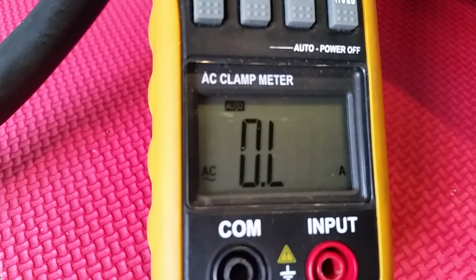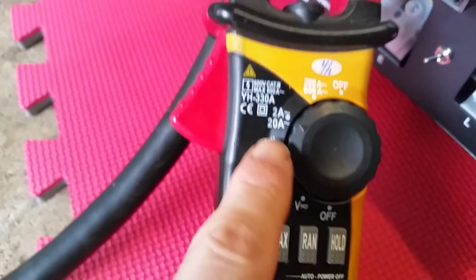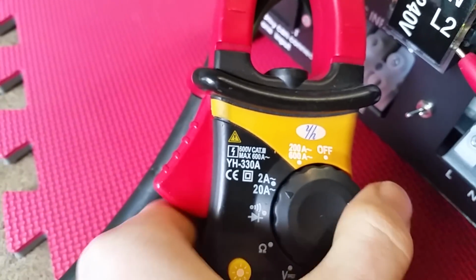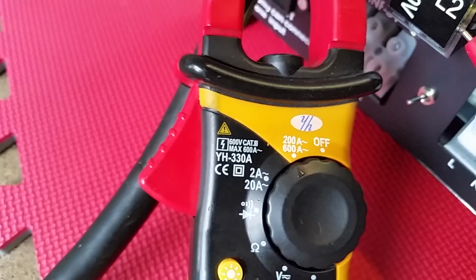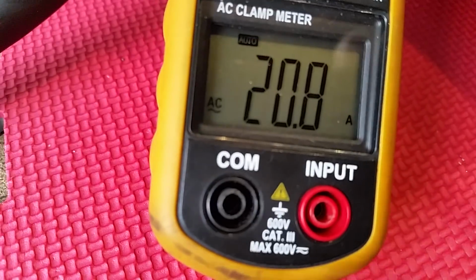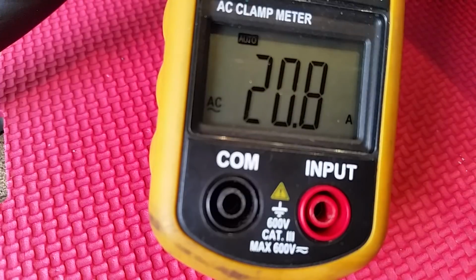Oh, overload. That's interesting. That's because this amp meter only goes to 20 amps. So now I've got to bump it up to the 200 amp, 600 amp range. Here we go, so I'm doing nearly 21 amps. And on my DC side I'm doing about 100 amps or so, fluctuating a little between 90 and 100.